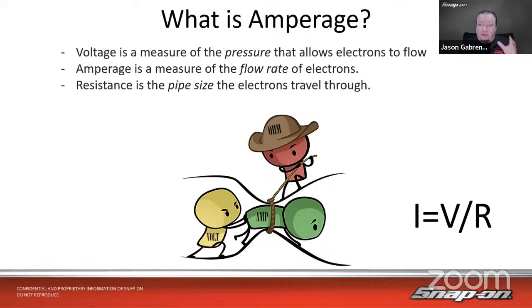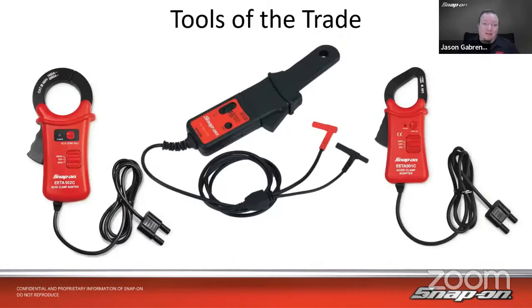So that is what we're measuring. We're measuring current, the amperage of what's flowing through a circuit, and we can tell a lot of different things by looking at that. So the different tools of the trade that we have—this is the most common one right here. This would be our low amps probe. Goes down to about 1 milliamp, up to about 60 milliamps or 60 amps or so. Anything more than that, you're going to want to get something a little higher.